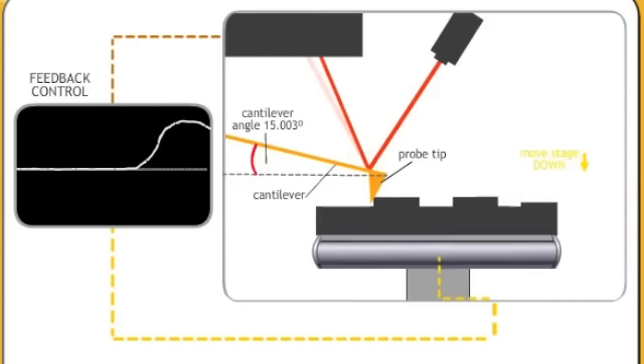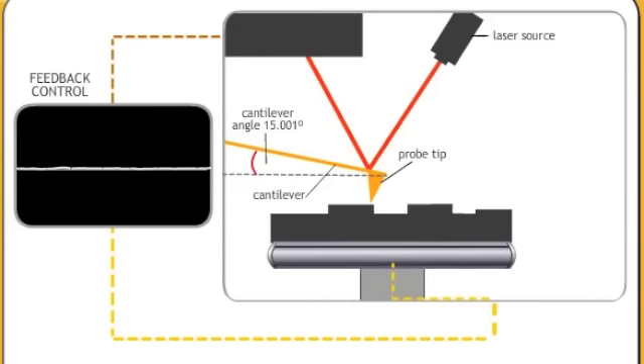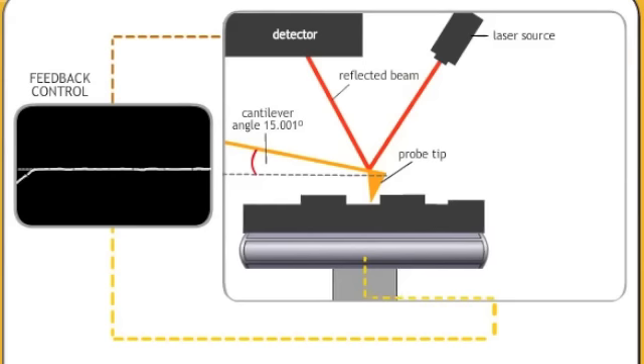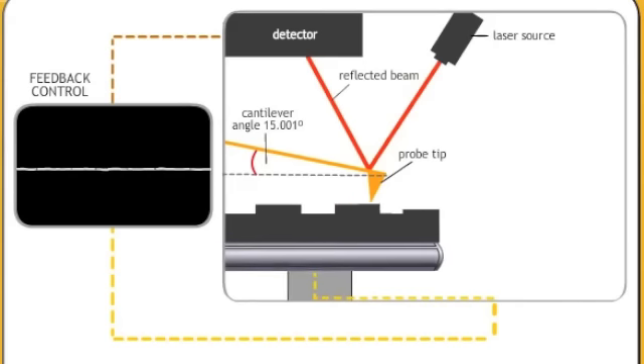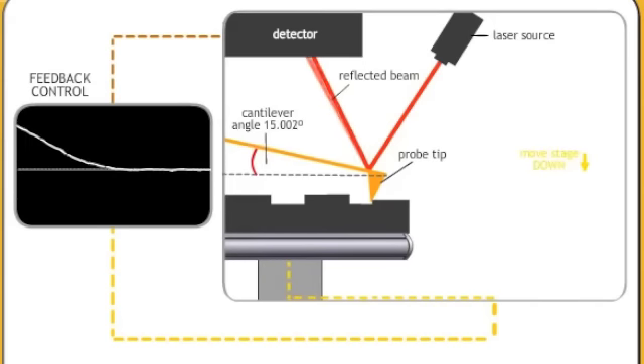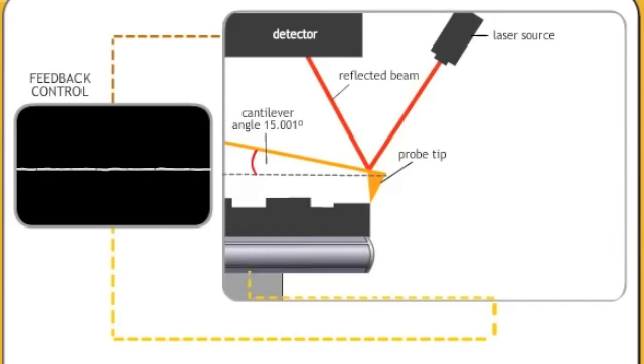A laser reflecting off the back of the tip moves up and down on the detector as the spring moves. The feedback loop reacts to change in the laser position by adjusting the height of the sample in order to keep the force constant.